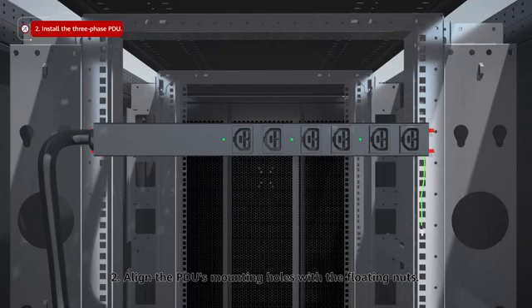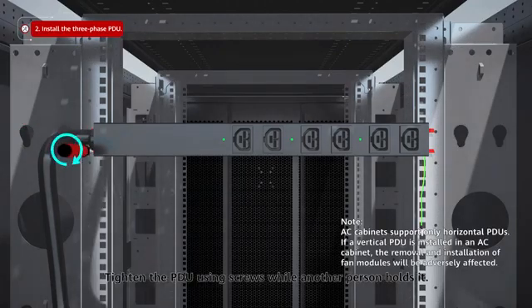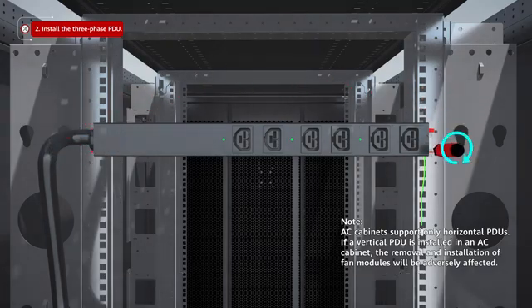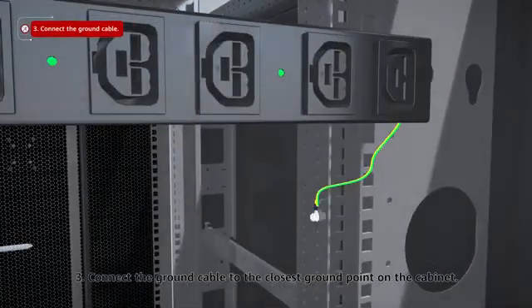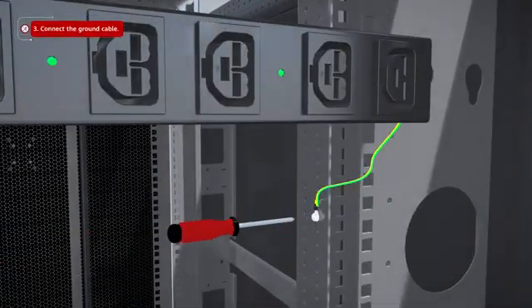2. Align the PDU's mounting holes with the floating nuts. Tighten the PDU using screws while another person holds it. 3. Connect the ground cable to the closest ground point on the cabinet.